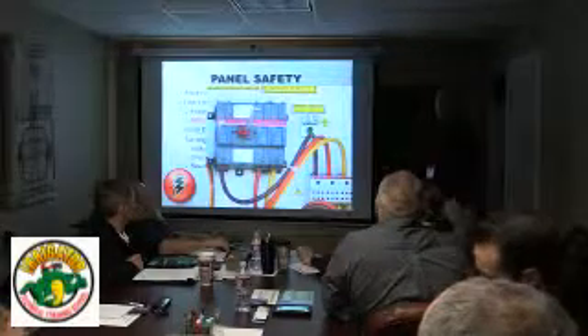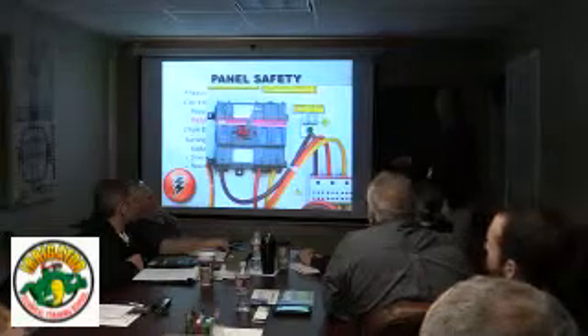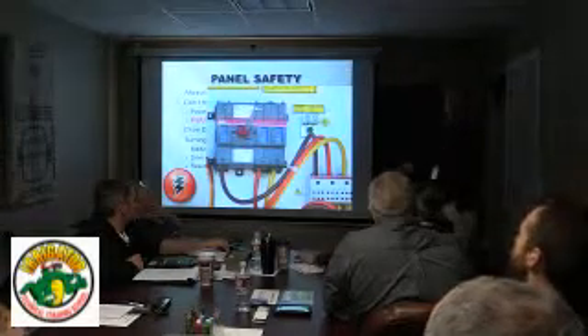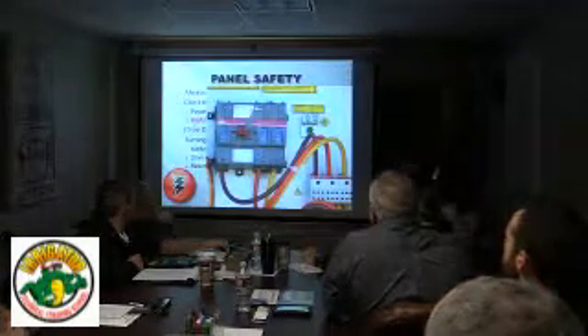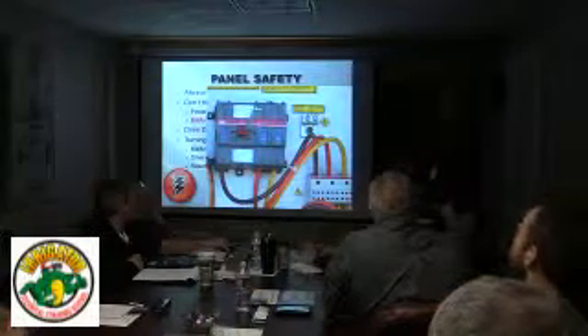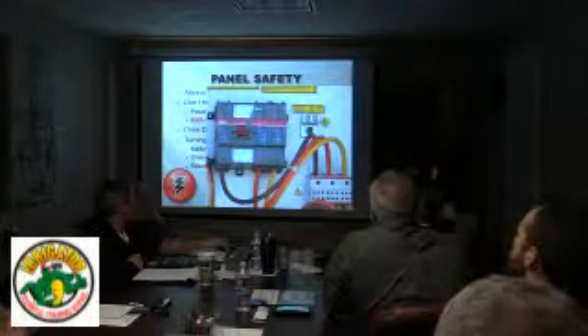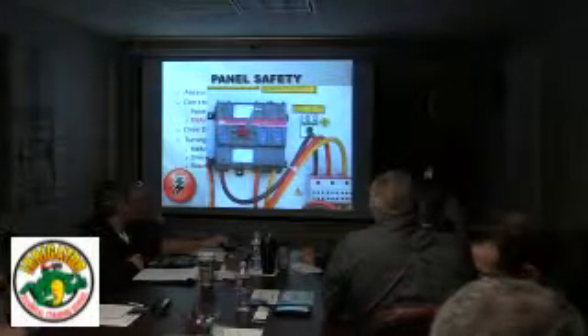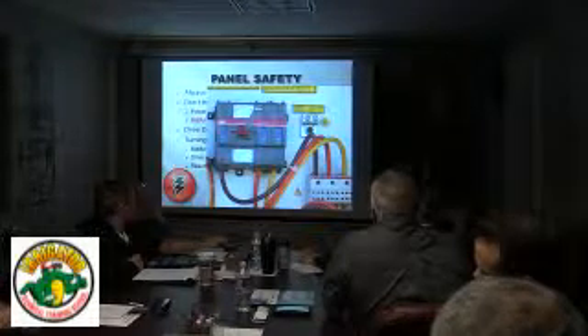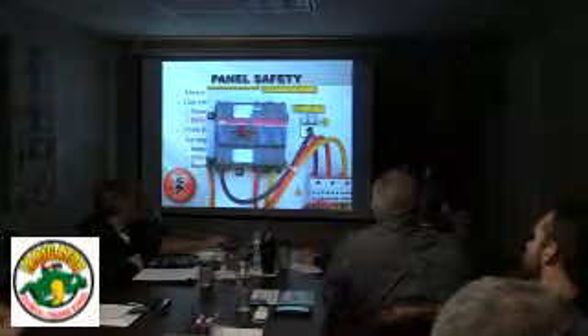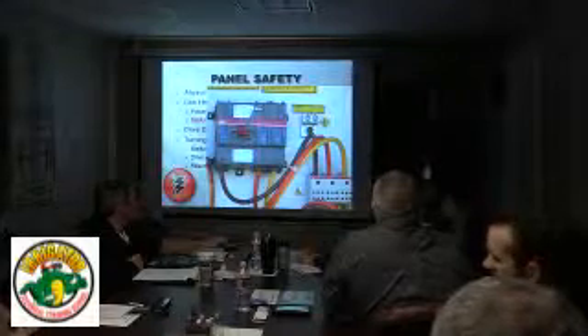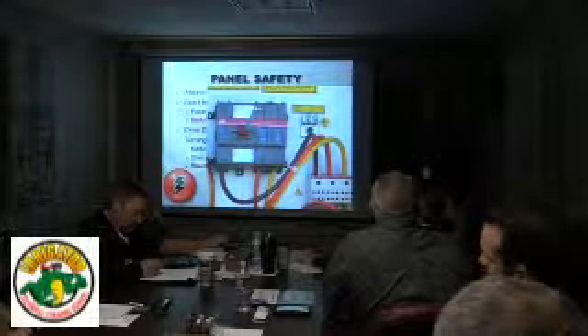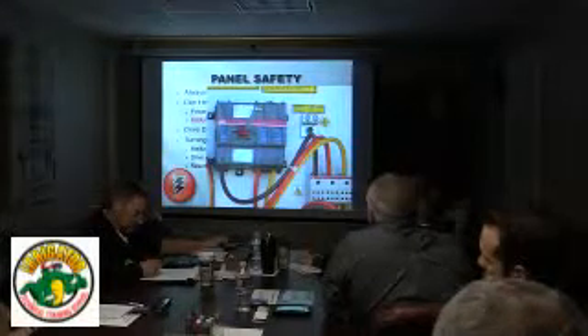Because you are ground, you're standing on ground, and if there's something wrong inside this switch or something else tied into there and one of these legs is hot but the other 2 are not, you may not measure anything across these 2 coming in with that off, but if there is a malfunction or something, you may measure from here to ground on one of those legs, and again, you are ground. So just be careful, use common sense.